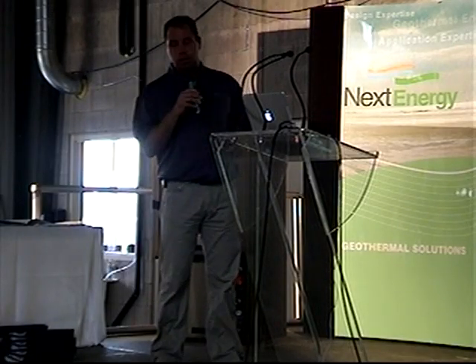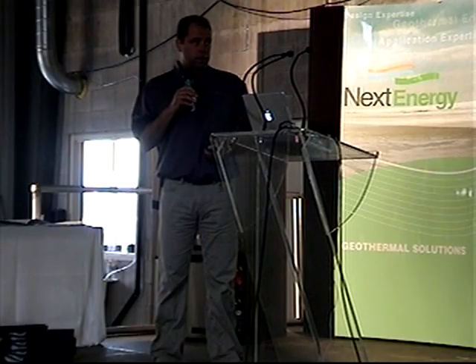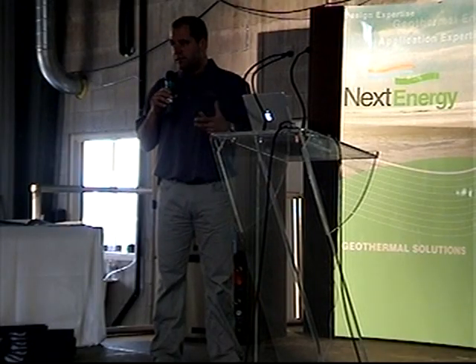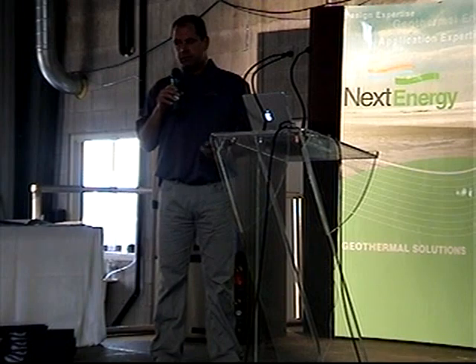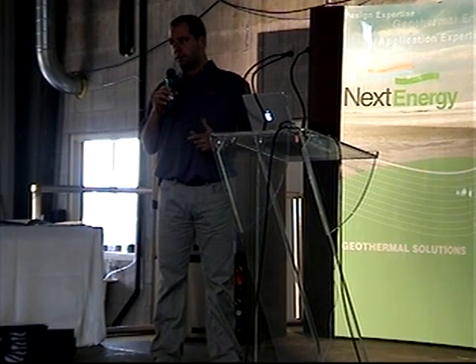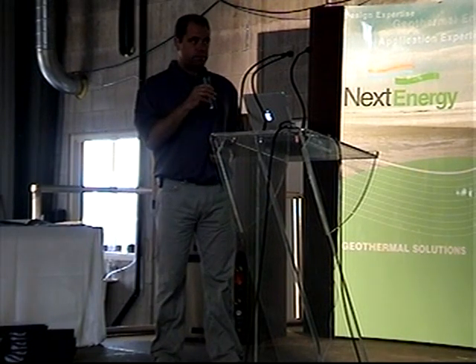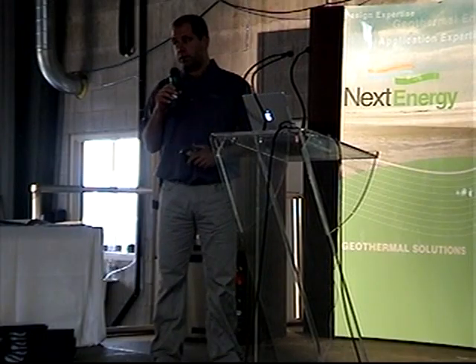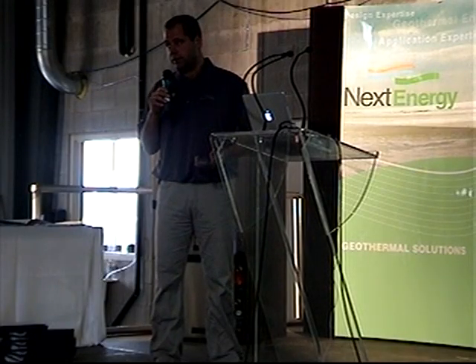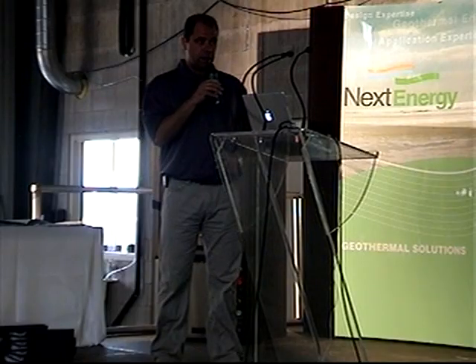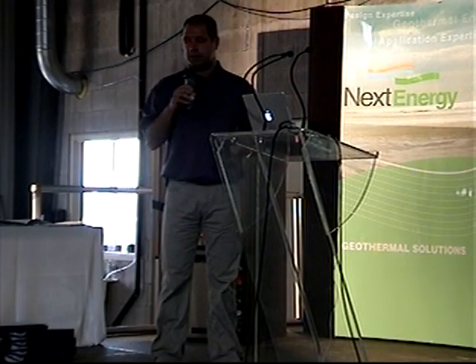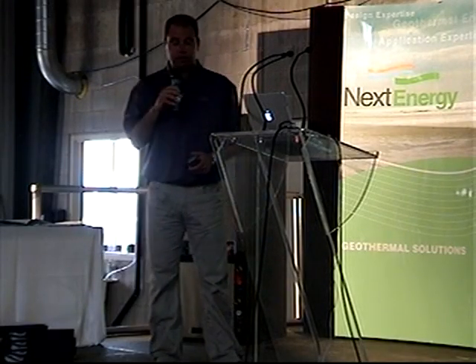There'll be some charts coming up later, but if a system runs out of gas and it's sitting there for a couple of days, you cannot just pull a vacuum on that system and recharge it. If it sits for a long enough period of time, you will have to change the compressor. And ClimateMaster knows that. It's just part of the industry now, nothing we can do about it.